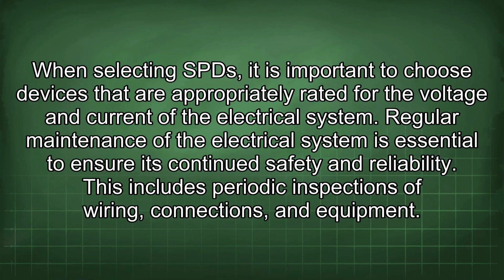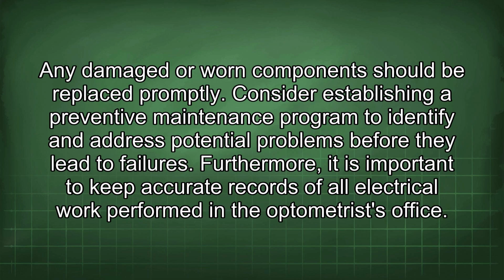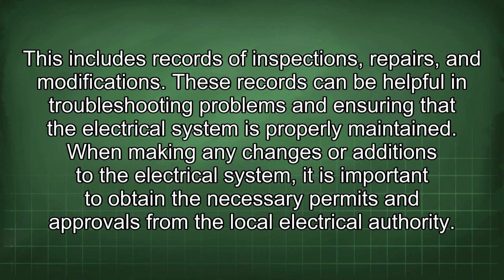This includes periodic inspections of wiring, connections, and equipment. Any damaged or worn component should be replaced promptly. Consider establishing a preventive maintenance program to identify and address potential problems before they lead to failures. Furthermore, it is important to keep accurate records of all electrical work performed in the optometrist office. This includes records of inspections, repairs, and modifications. These records can be helpful in troubleshooting problems and ensuring that the electrical system is properly maintained.